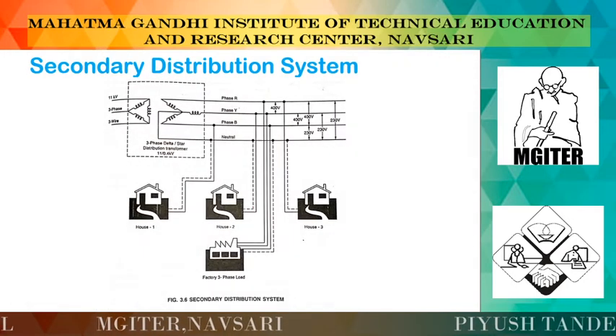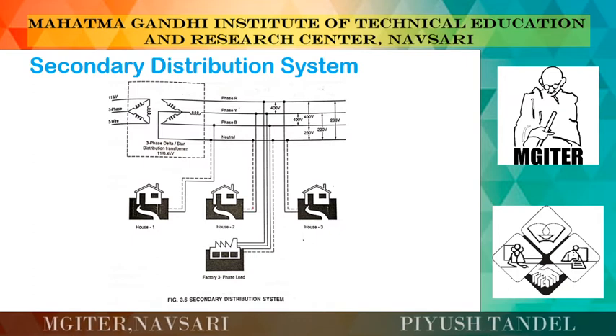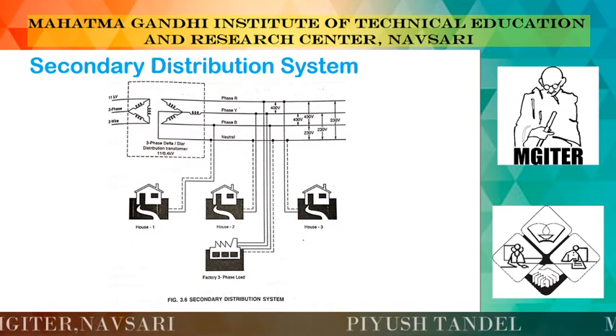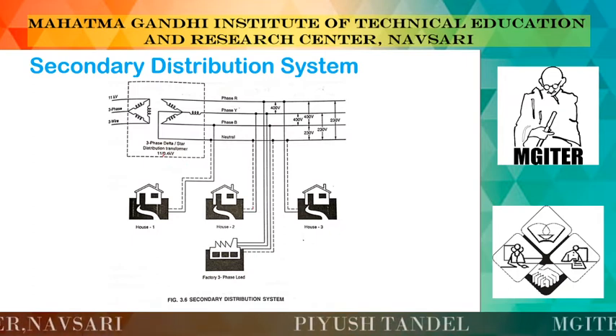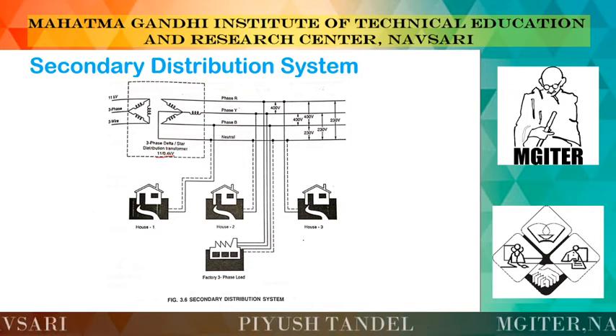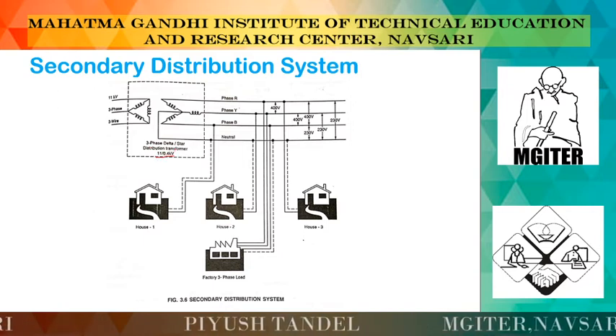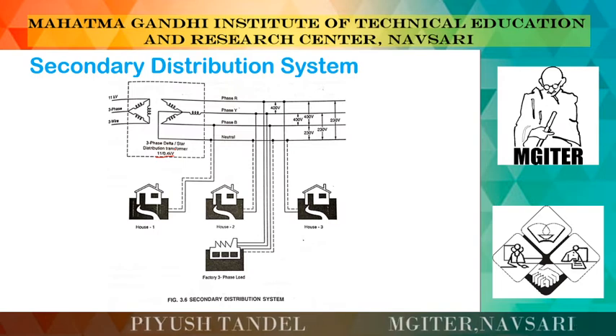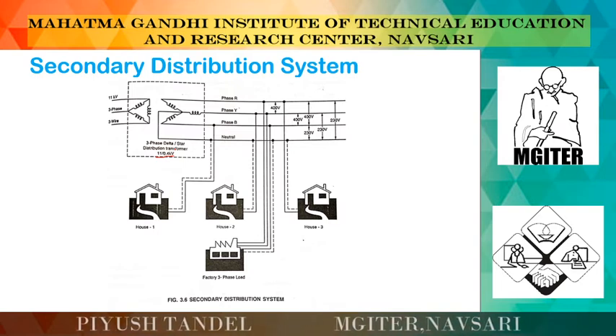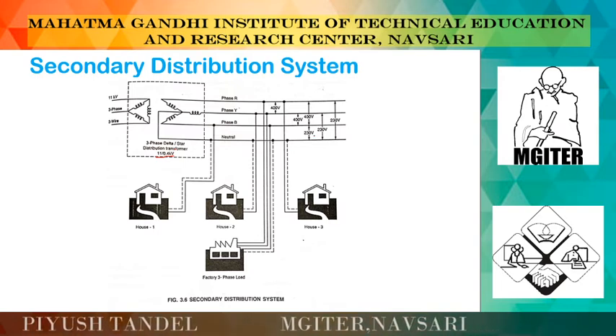Now the secondary distribution system: at a distribution substation the voltage is stepped down to 400 volts, right? Here we convert from 11 kV to 400 volts. From this station the voltage is at a low level, that is 400 volts, and between phase and neutral we can call it 230 volts.